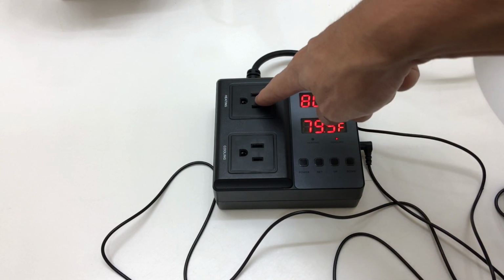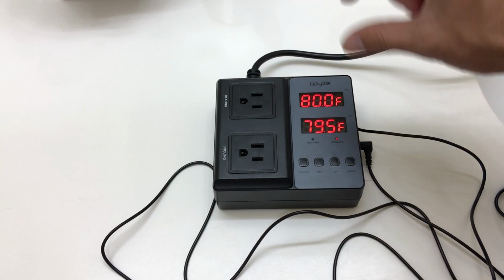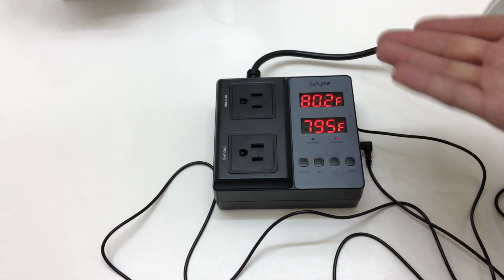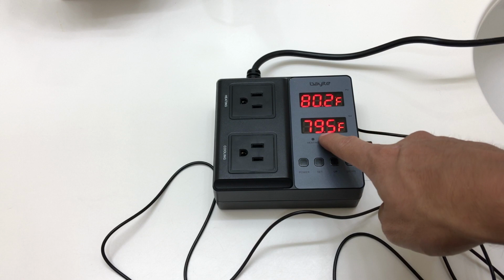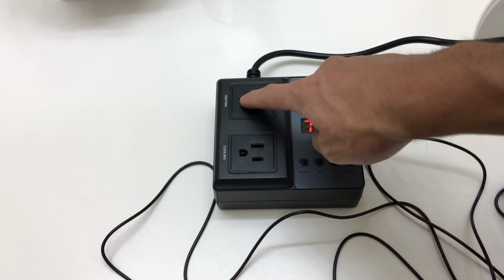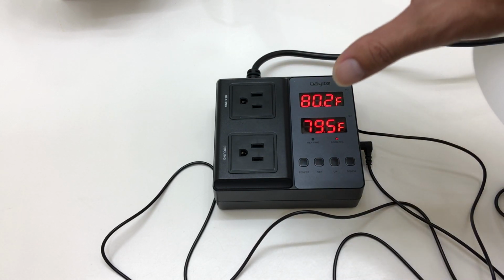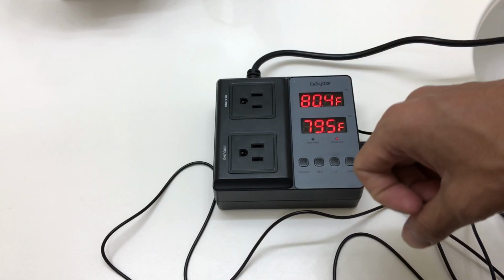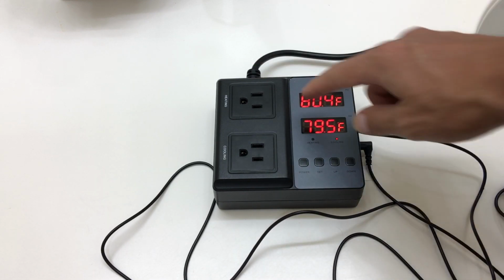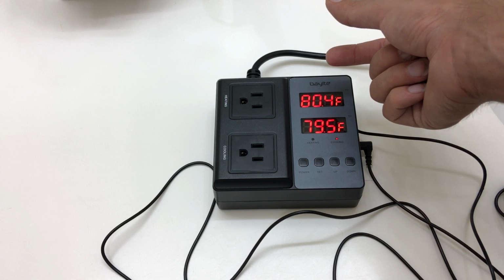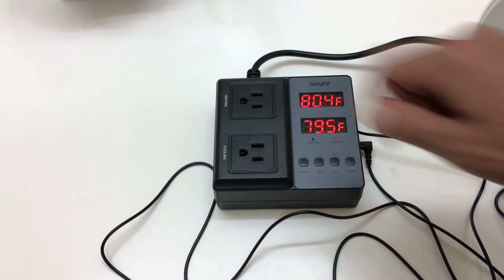And guys, when running the heater, remember to set its temperature higher than the temperature you're trying to hold. Because if you set it to exactly 79.5, the probe on the heater itself may shut it off and render this controller useless. So you have to overshoot your heater setting a little bit so this can operate properly.